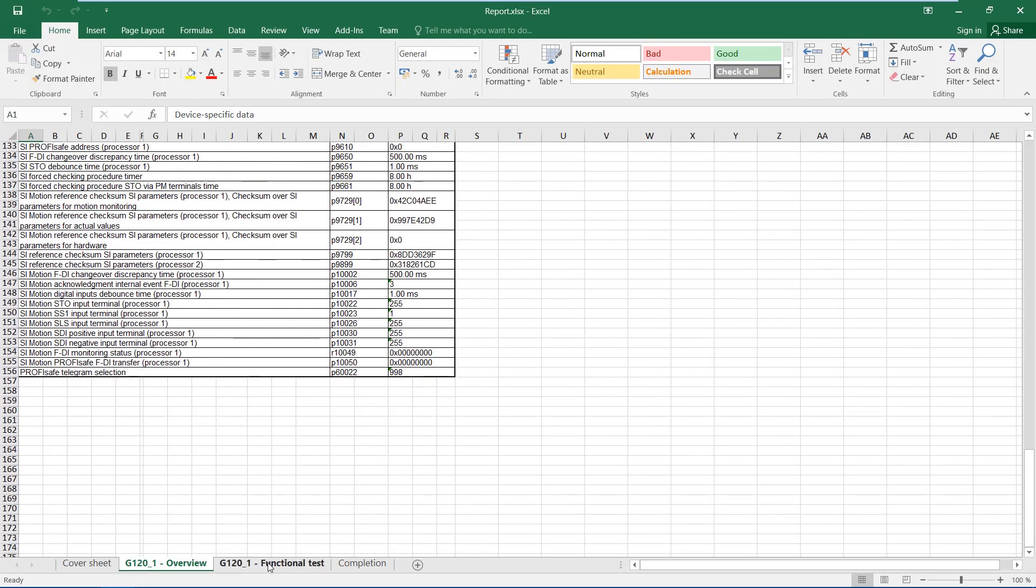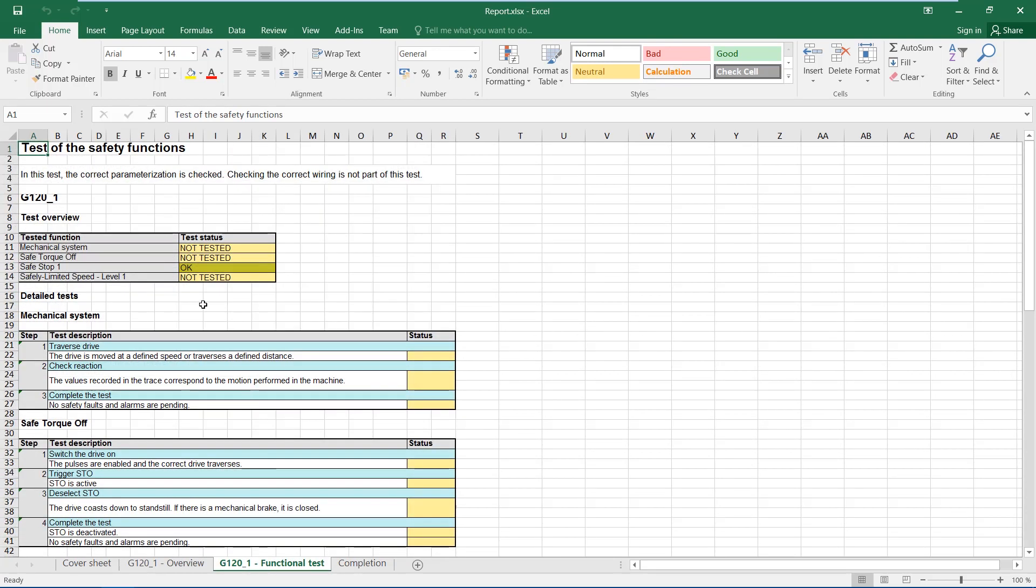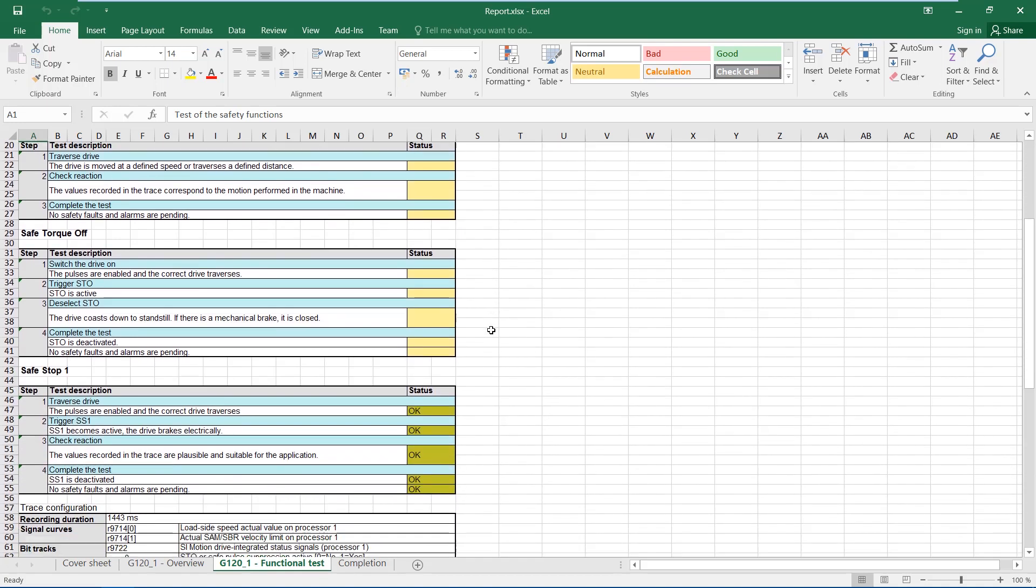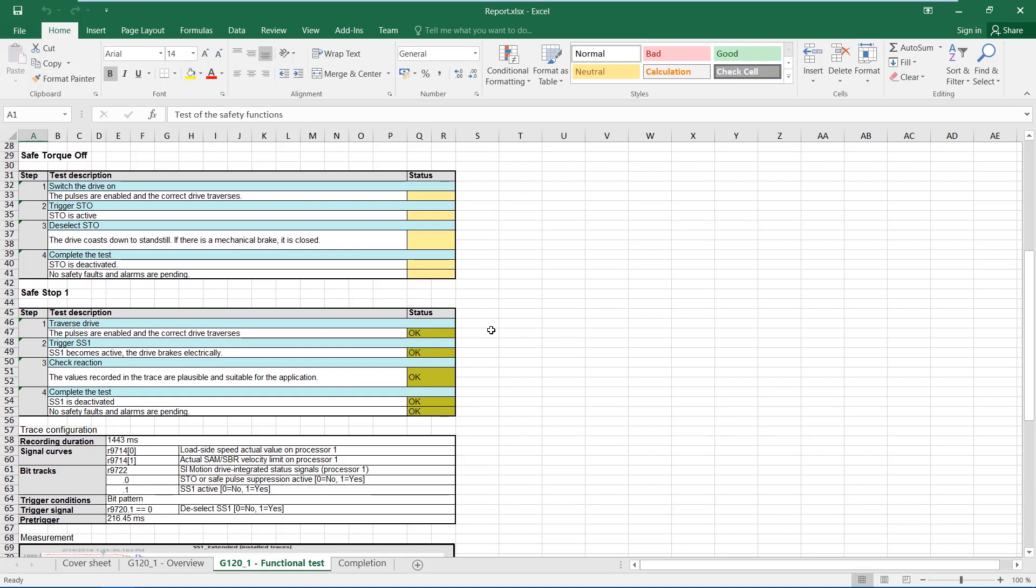The functional test sheet provides an overview of the individual test steps. The mechanics, safe torque off and safely limited speed have not yet been tested. In safe stop 1, each step was completed with okay.